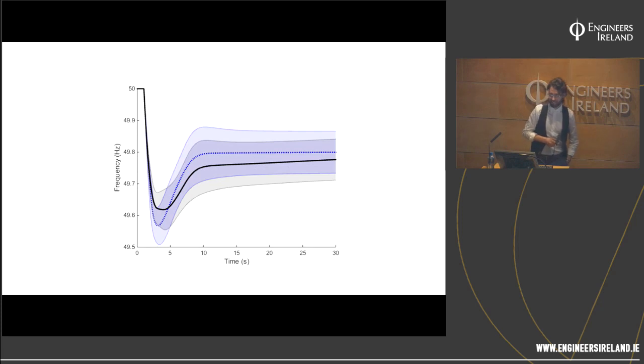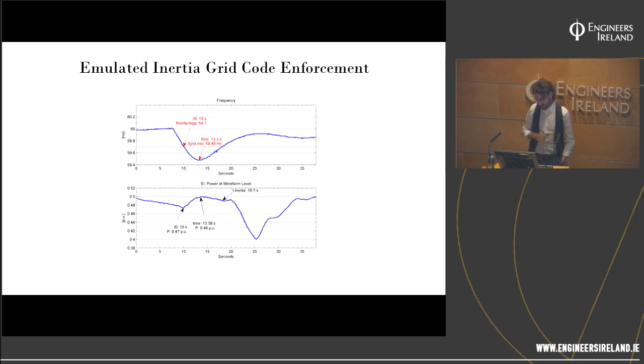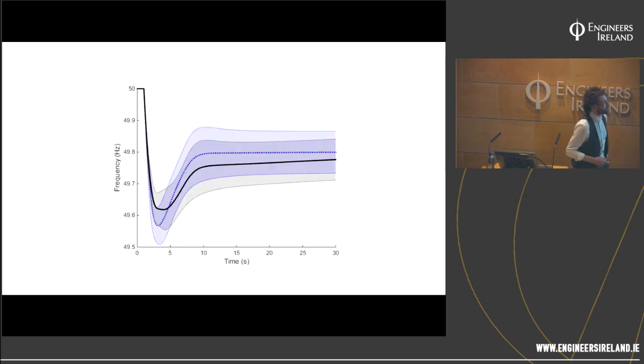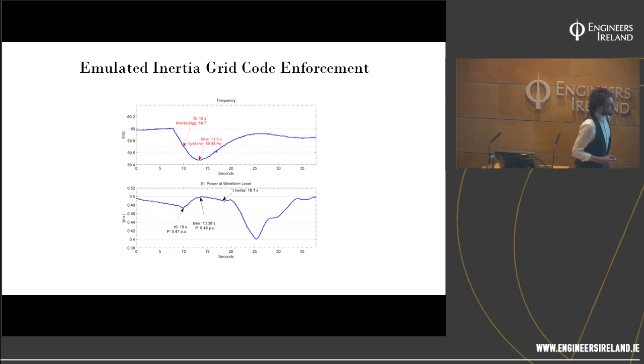I suppose these are my lovely simulations rather than the real world. So Hydro-Quebec in Canada actually has a grid code requirement for all wind farms over a certain megawatt size to have emulated inertia. And this is the response from a turbine, I'd say, by power at the wind farm level, to a drop in grid frequency. One of the interesting things to point out here is that just before the event happens, the wind power output is falling. So if the event was to happen here, you probably would have been in a better spot. But because the wind is falling, and again that doesn't happen in my simulations, where you have constant wind speed, the wind is falling, and then the inertial response kicks in, and then you have your energy recovery.